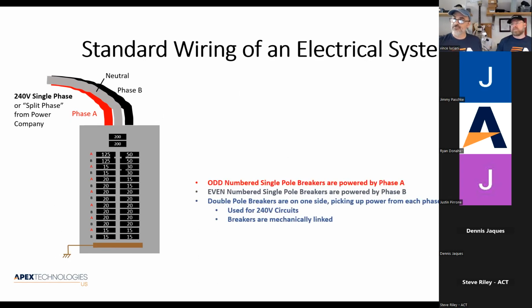So in the breaker panel, if you go down the left side or the right side, I just have the left side marked here. The two phases alternate. So the first breaker is phase A, then phase B, then A, B, A, B, A, B. The reason why they do that, if you can see on your screen that top breaker that is 125 amps, there's usually a little metal clip that goes over the little actuators, right? The little handles on there.